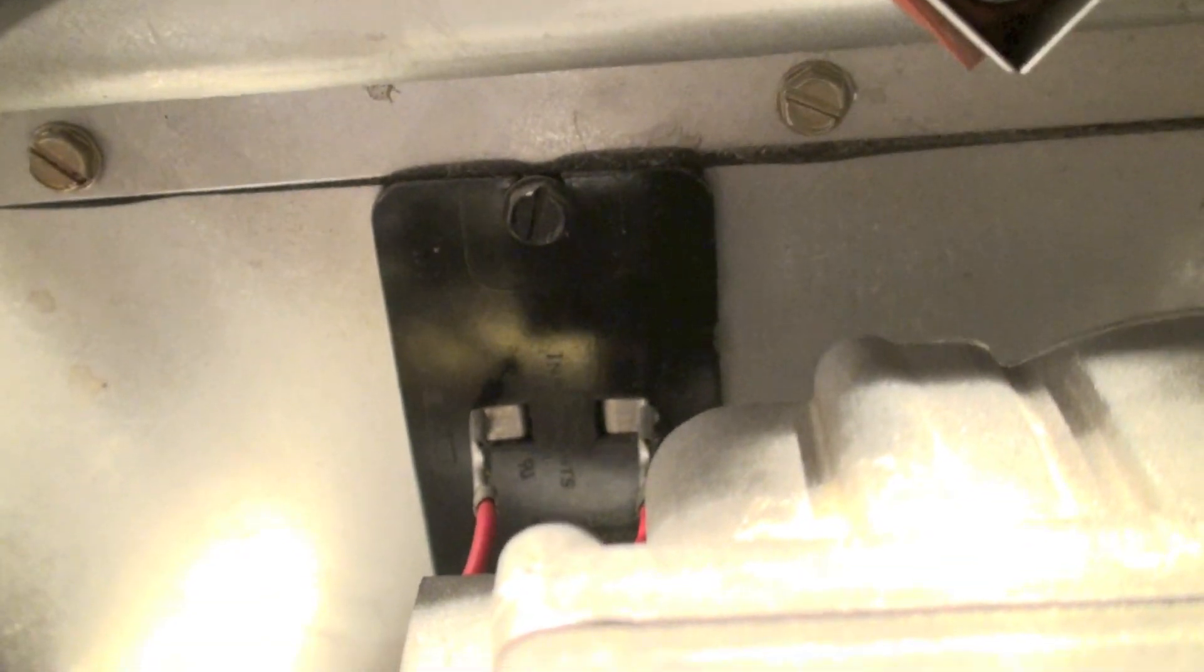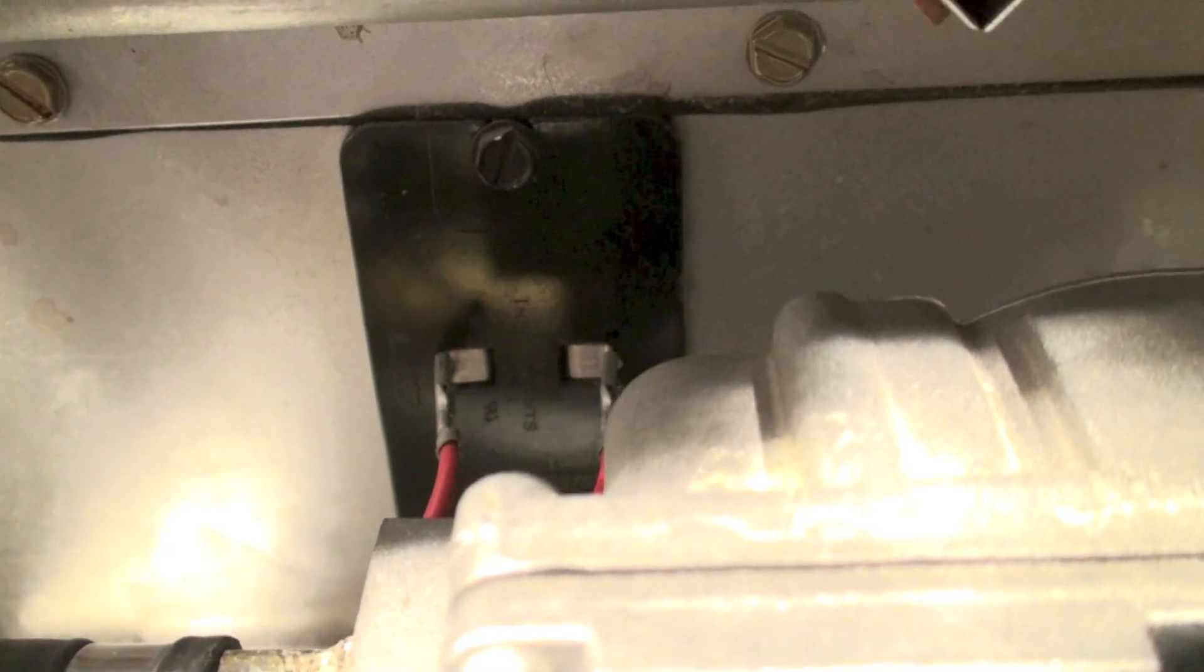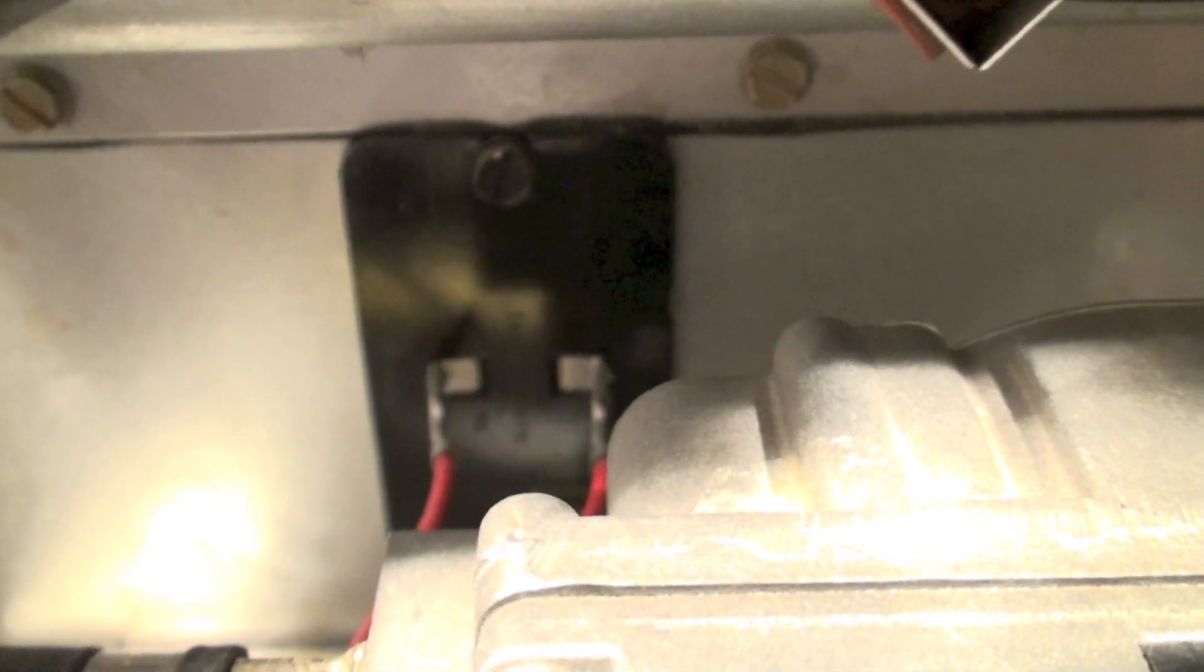Now, in order to test this, we do not disconnect the wires. We overheat the furnace, just like it would happen in the real world. So, how do we do that?